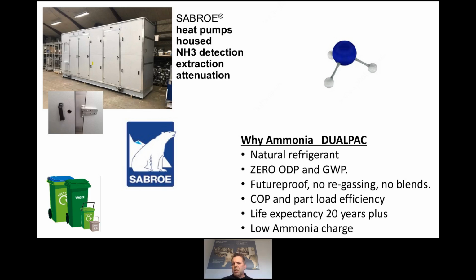In a HFO-HFC system, you have a blend of gases. If you have a leak, you will lose a percentage. Therefore, to regain your efficiency, you have to evacuate the system and replenish with brand new gas. So this is very expensive, whereas this is not a blend. Good COP expectancy, industrial build 20 years plus, low ammonia charge. And if you want a simple life, we can simply give it to you in a housing with detection, extraction, attenuation, much easier on site.